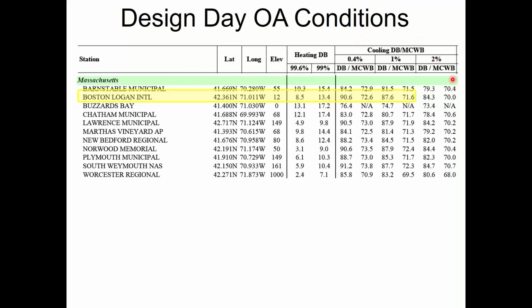For cooling, I actually get 3 columns. And it works the same way, it's just worded weirdly. So the 99% column for heating is the same as the 1% column for cooling. It's just a bell curve, and they're telling you whether you're on the 1% side of the curve or the 99% side, but it means the same thing, right? So this means 1% of the time it's above 87.6 degrees in Boston on a 30-year average. 0.4% of the time it's above 90.6. There's also a 2% column. I've never seen anybody use that, so I don't even bother highlighting it. Most people will use the 0.4.